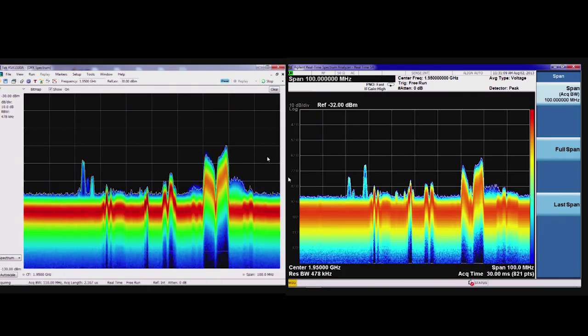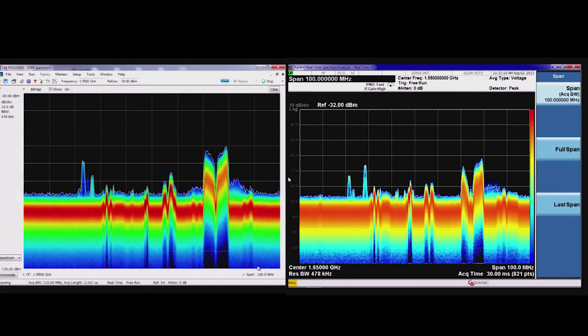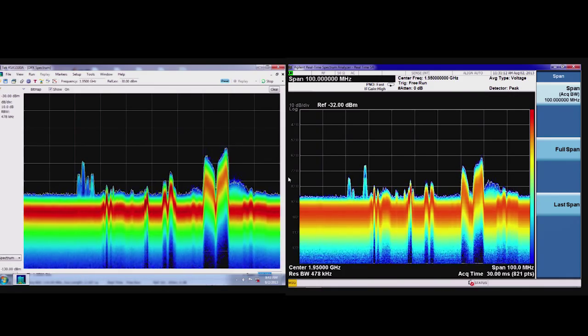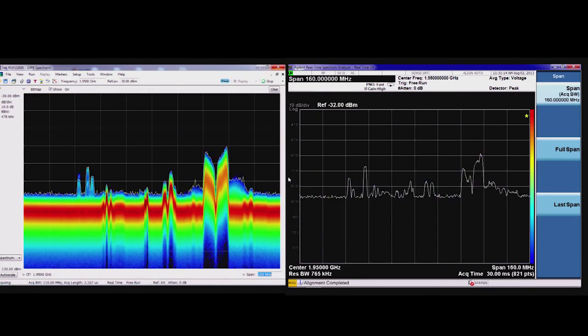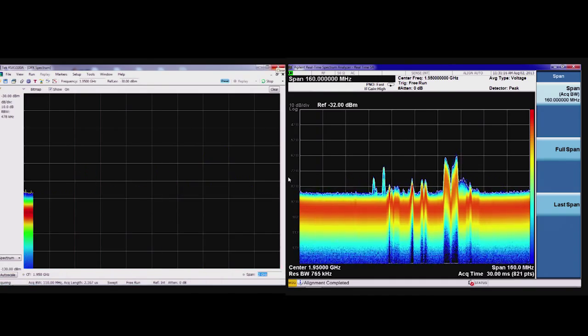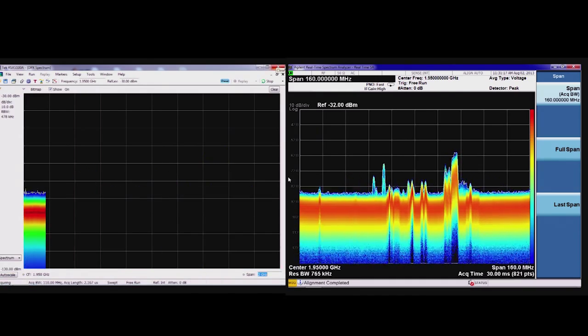On the left-hand side, we see the Tektronix instrument. On the right-hand side is Agilent, both looking at about 1,900 MHz for the US cellular band.